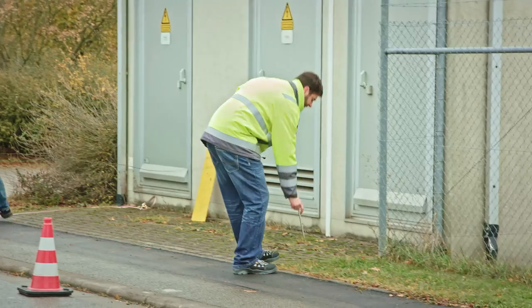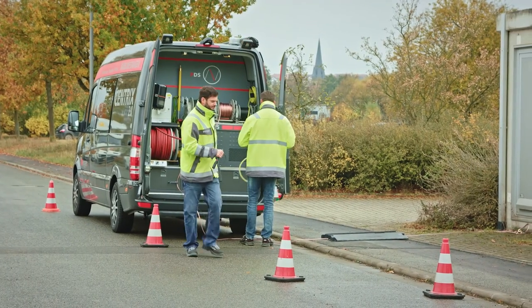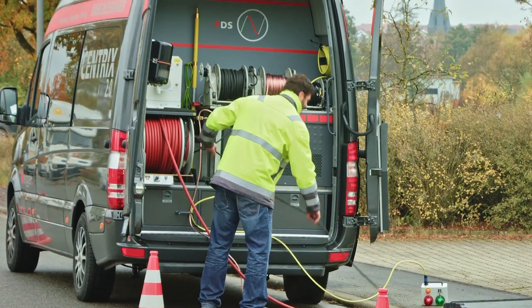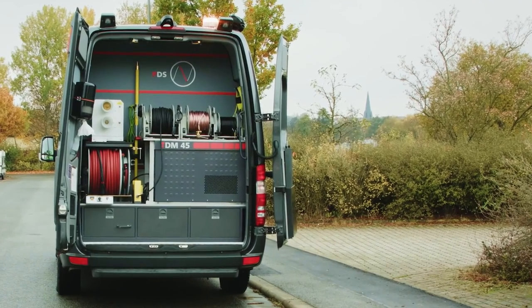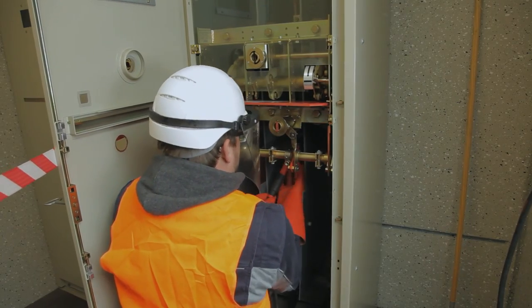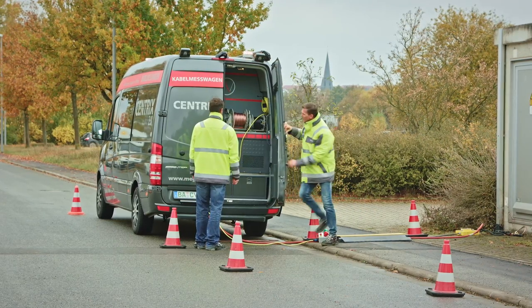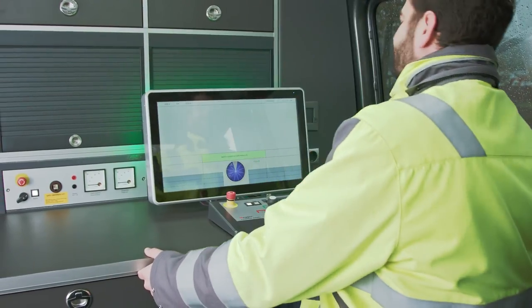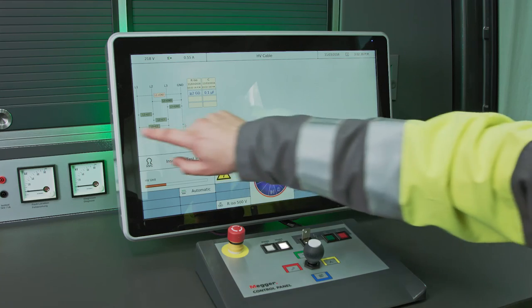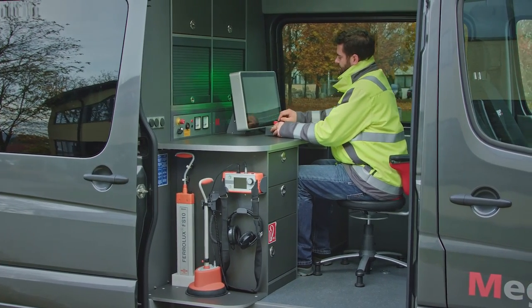Up to eight pre-location methods and four different voltage waveforms are available for cable testing and diagnostics. All our high-voltage test and diagnostics technology is van integrated. No matter the weather, measuring partial discharge is possible without issue, even in compact substations. A unique operating concept with automated test sequences via rotary knob or touch display simplifies operation significantly and allows quick and intuitive location of cable faults.